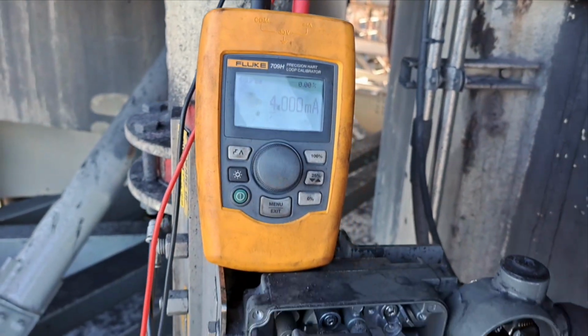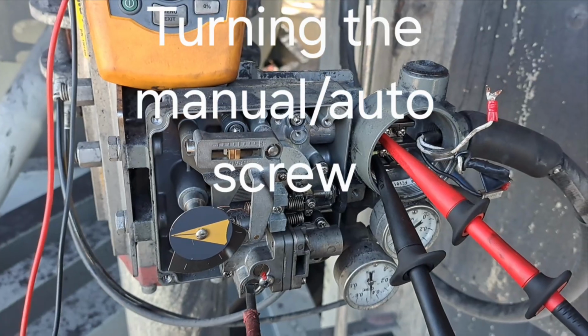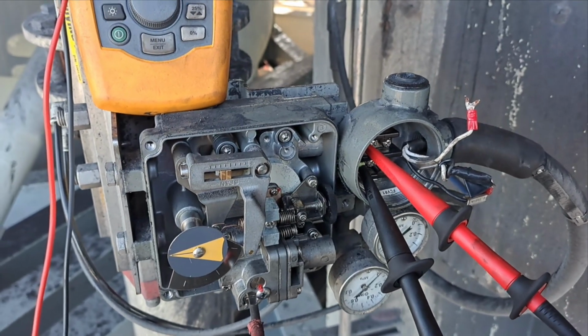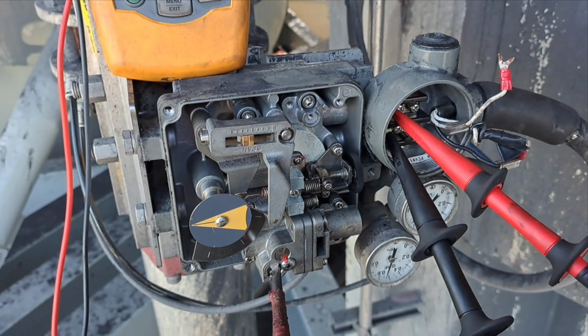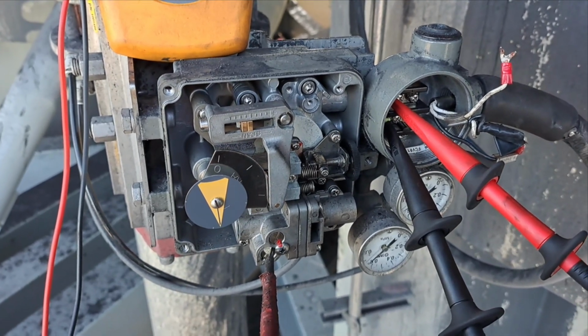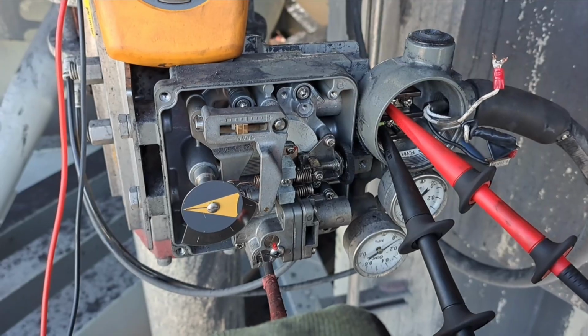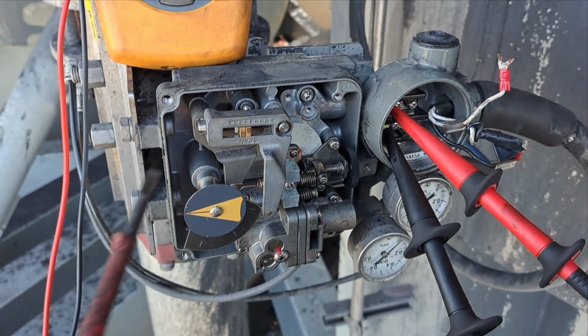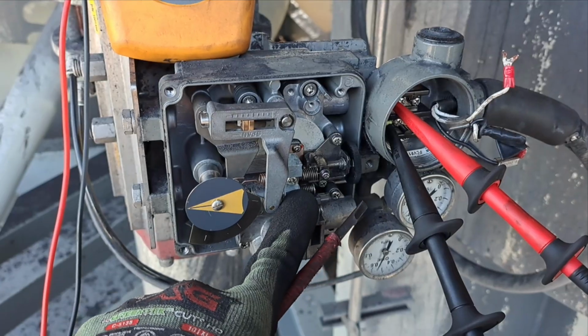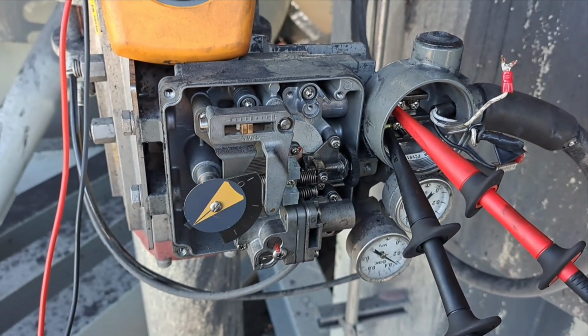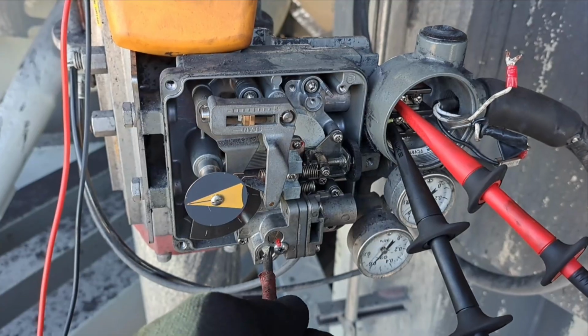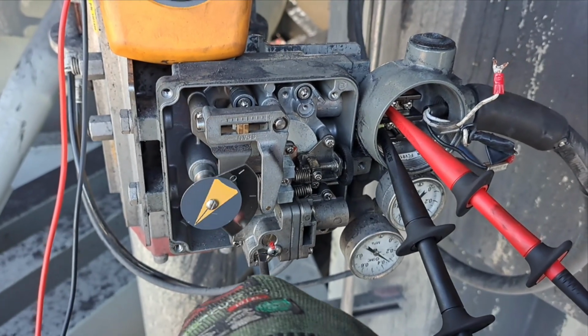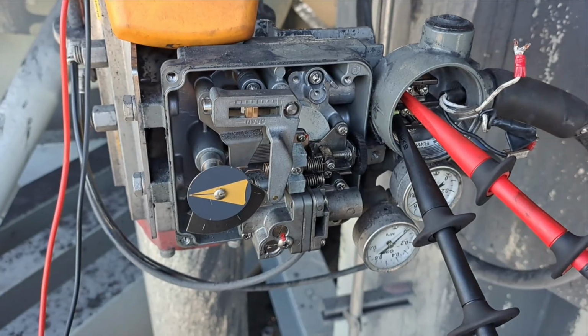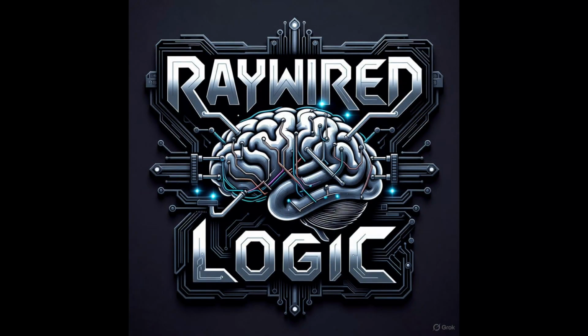Now let me show you another way to toggle the pilot valve. This method only works when the signal is not at 20 milliamps, in other words in the open position, or if the cable signal has been disconnected. I think I'm done, but I'm going to get the operator to control the valve in manual from the control room, and a bit of patience is required for these steps.